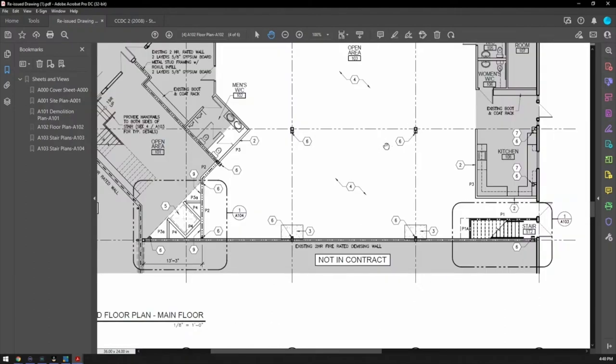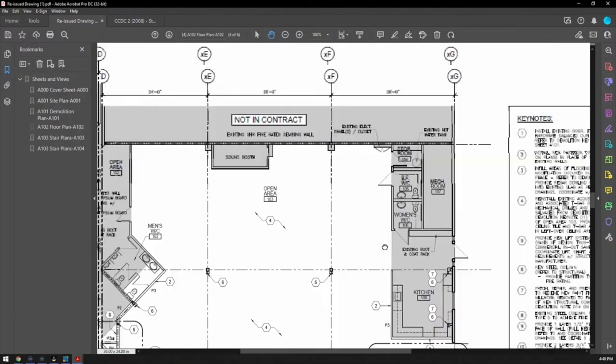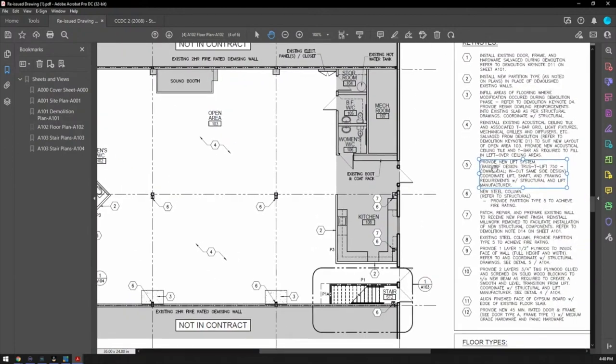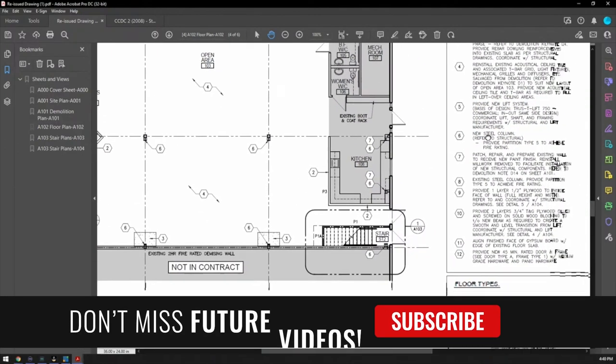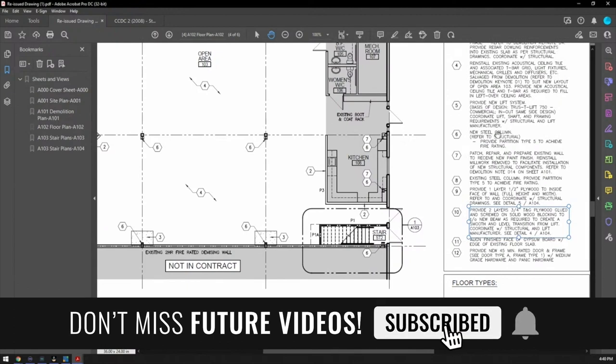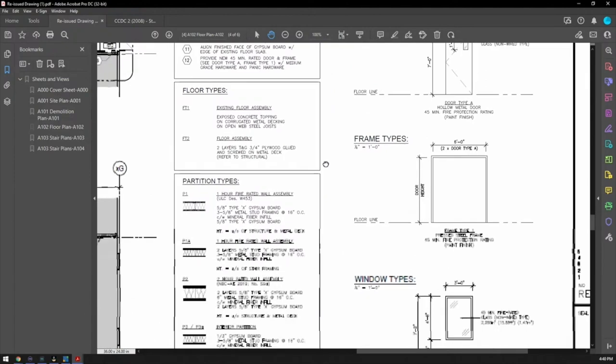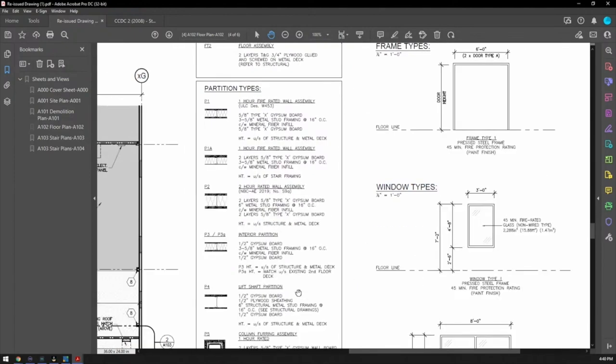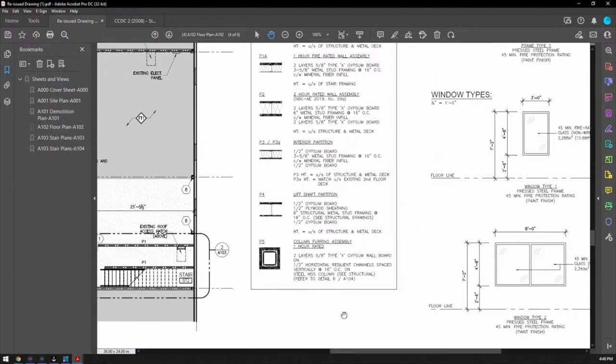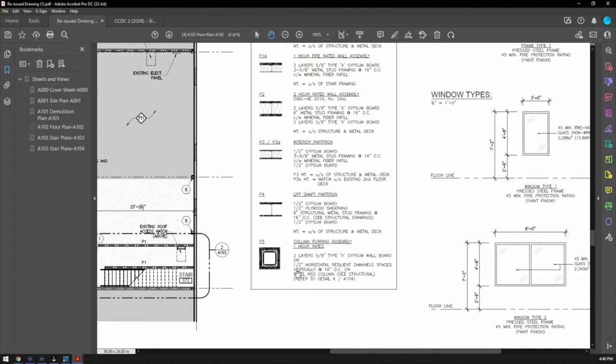See this here, six, six, six, six, six, six, or whatever. That's referring to this side right here, six new steel column. This also doesn't tell you, all right, you got to go over here to the partition type, which is crazy because it's usually not here. So column one hour assembly, two layers of five-eighths type X. So this has to be, all the columns we did there had to be double wrapped. And that tells you here, horizontal resilient channel spaced vertically.